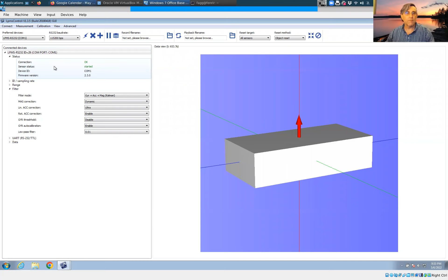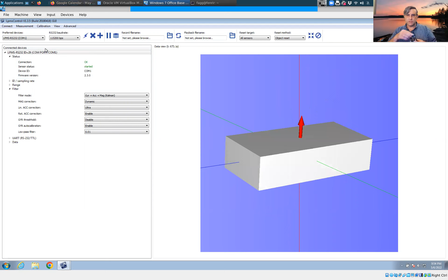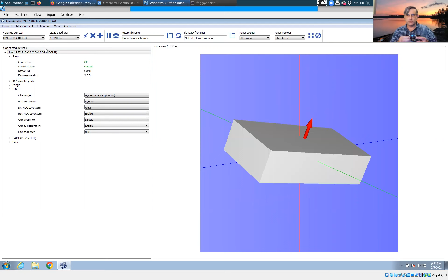I'm not sure. One can also calibrate the zero, which is probably a good idea as well. So we can set offset, in which case the sensor really should be flat when we do this. And then finally, I do a save parameters to sensor just to be sure that everything gets written properly. And then at this point in time, if we start the sensor off in its zero orientation and move 90 degrees in each of the cardinal directions, then we should see that same change in the box there.